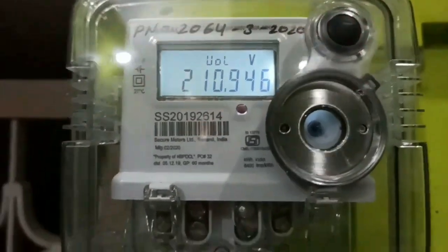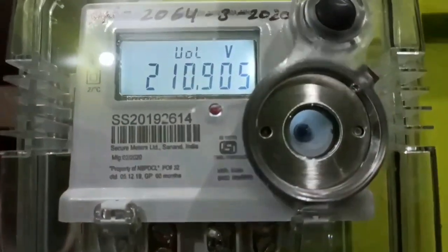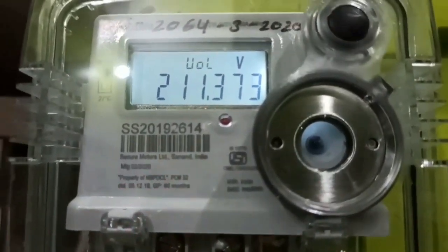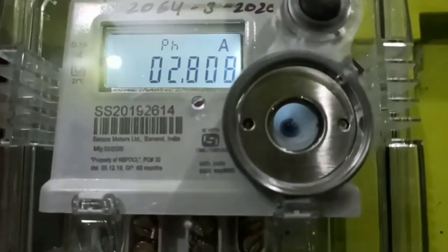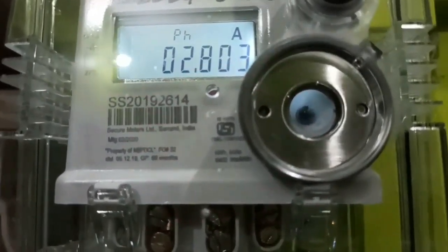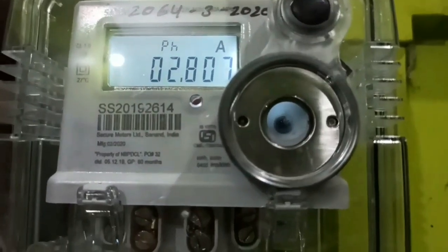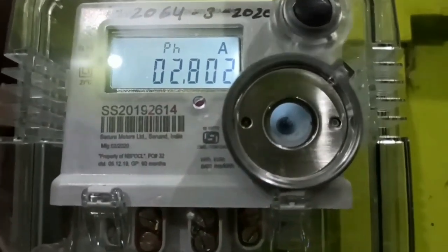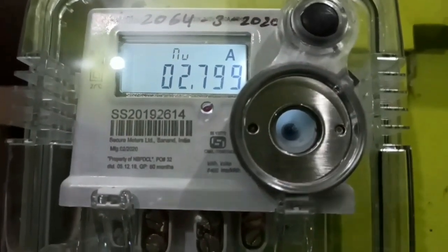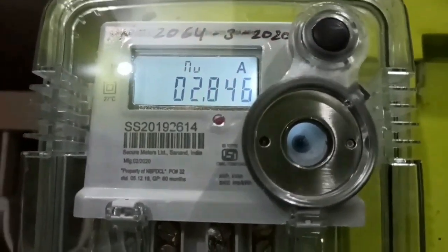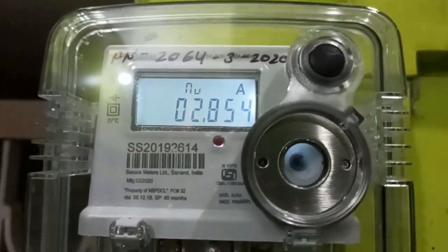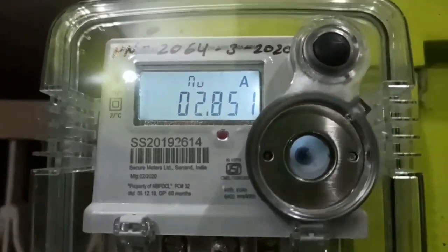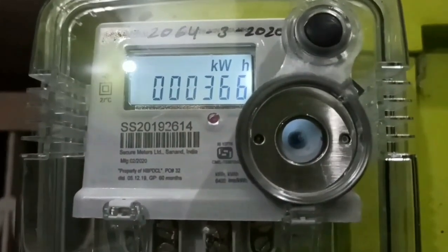And then we'll keep seeing what is the next data. Now the voltage, 210 is good enough, because it's quite at some distance from the transformer. That's why we are getting this much. If we are near the distribution transformer, we will be getting a good voltage of 240. And then the phase current, whether we take neutral or phase, doesn't matter, it is 2.8. From here you can calculate the power also. 2.8 multiplied with your recorded voltage of 211, you get around 500 watt. All right, so this is how you calculate. It keeps changing because it's not constant.